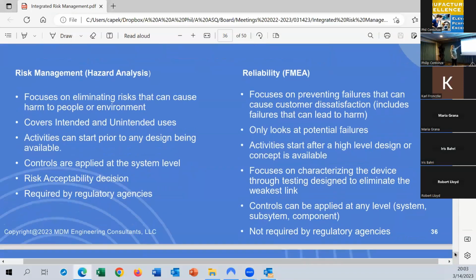on preventing failures. Sometimes hazards can be caused in normal circumstances, conditions, right? And you still need to be able to address this. The risk analysis covers intended and unintended uses, and it covers activities that can start prior to any design being available. But an FMEA is only valid once I have at least some level of design, because I need to know what my items are, what their functions are, and how they can fail. I can start a hazard analysis just by looking at the intended use of what I'm going to have, at a very high level.